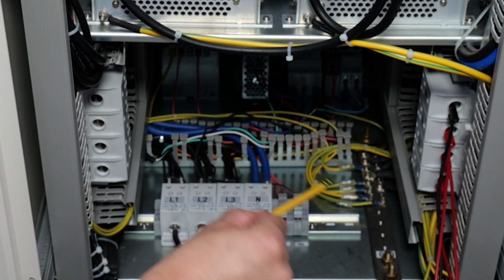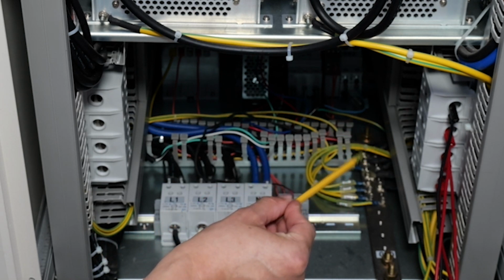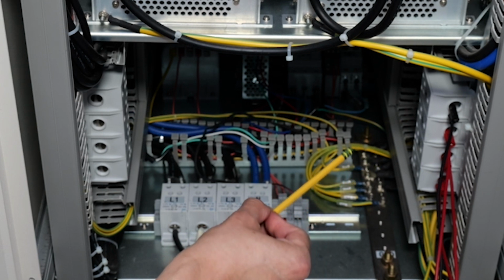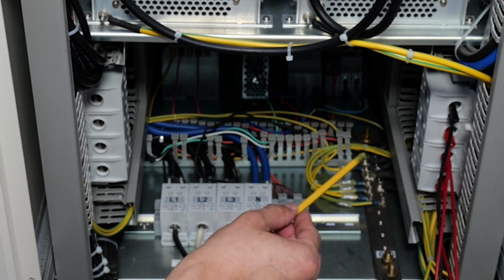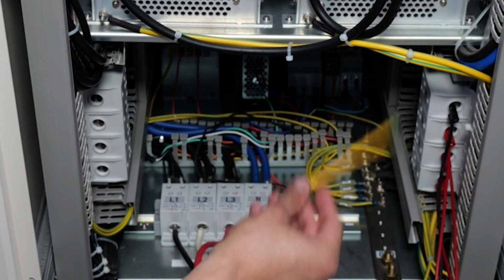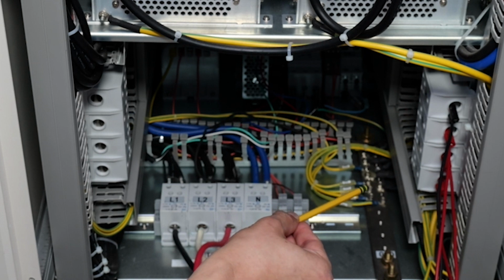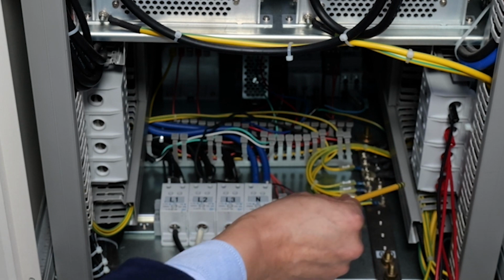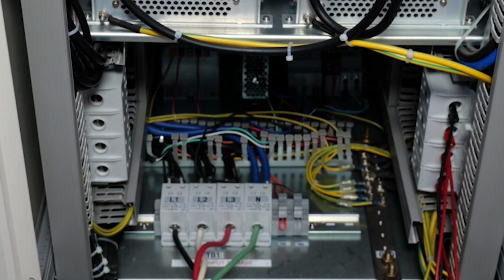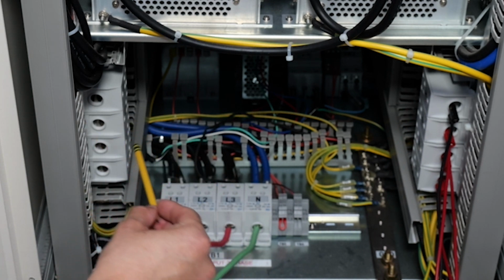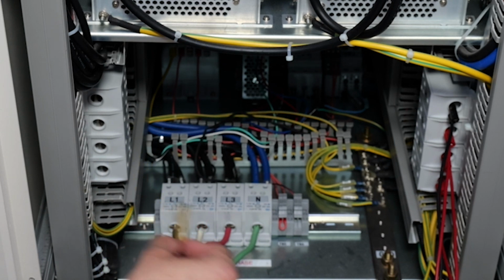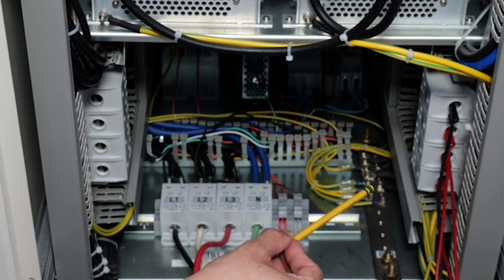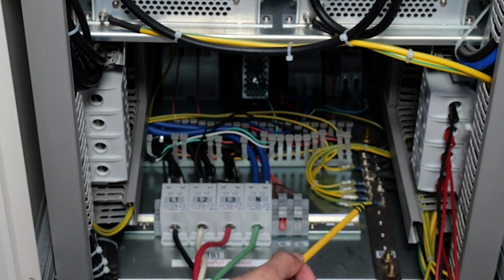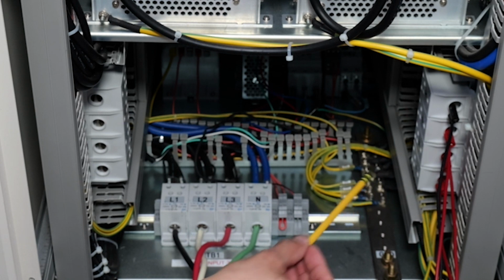But on the right, you're gonna see a terminal block with A, B, C, and neutral. So that's actually the power coming from our programmable power supply going to the EUT. For this demonstration, we have a three phase circuit connected, but since we're only gonna do a single phase 120 volt test, we're only gonna energize line A and neutral. And on the left, you're gonna have the same 480 volt bus that you could use to power on accessories, or you could power on the EUT from this 480 volt. But today I'm not gonna be using that voltage since I'm using 120 volts.